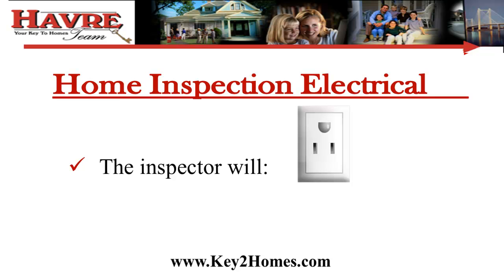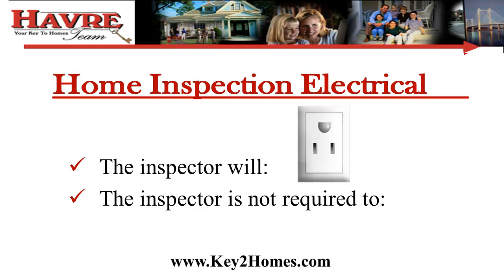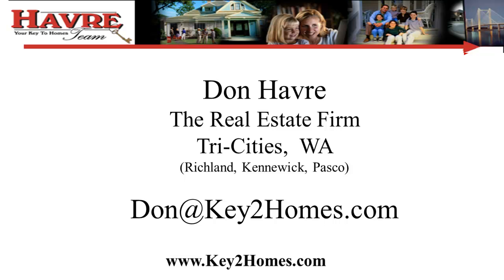The report should indicate, if present, solid conductor aluminum branch circuits, and include a statement in the report that solid conductor aluminum wiring may be hazardous and a licensed electrician should inspect the system to ensure its safety. Now, the inspector is not required to insert any tool or probe or testing device into a main or sub-panel, activate electrical systems or branch circuits that are not energized, or operate circuit breakers or service disconnects, or remove fuses. So that's the first part of what goes on during the home inspection.